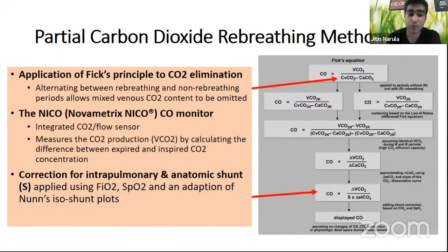A correction is applied for the intrapulmonary and anatomical shunt using the FiO2, SpO2, and an adaptation of Nunn's iso-shunt plots. The monitor consists of a simple kit which has a CO2 sensor, a rebreathing loop, a disposable airflow sensor, and a pulse oximeter. The computer cycles every 3 minutes from the non-rebreathing mode to a 50-second period of rebreathing by adding an additional dead space with a disposable rebreathing loop. A ratio of change in carbon dioxide elimination and the end tidal carbon dioxide after partial rebreathing allows us to calculate the cardiac output.